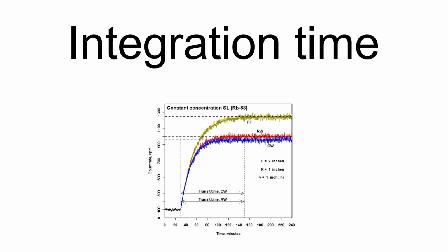The count rate of the monitor varies dynamically, so that a measurement time interval must be specified. Also, these are integrating devices, meaning that some finite time is required to accumulate radioactivity onto the filter medium. The input to the monitor is, in general, a time-dependent concentration in air of the specified nuclide. However, for the calculations given below, this concentration will be held constant over that interval.